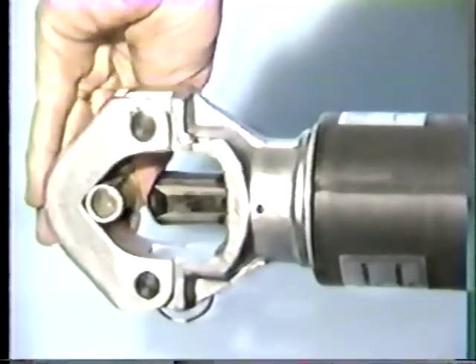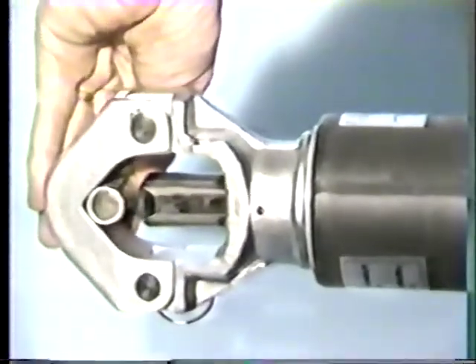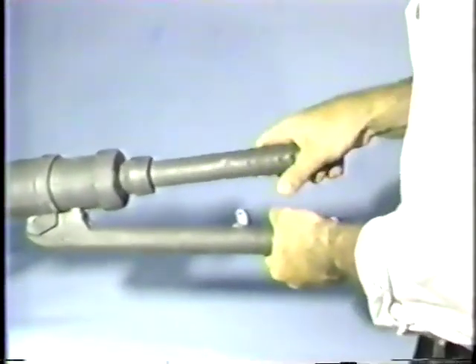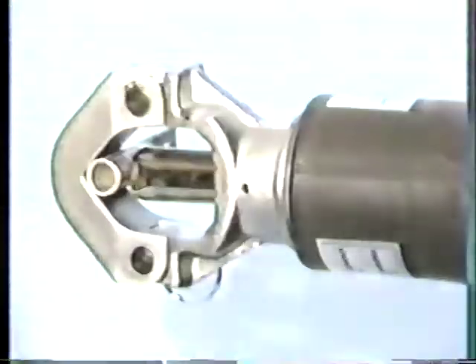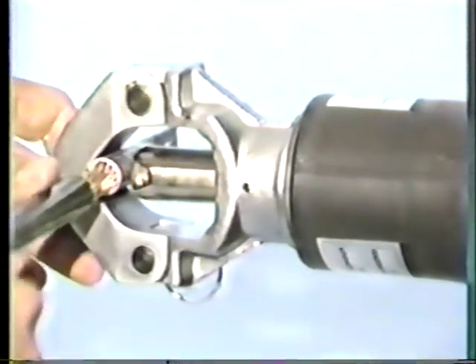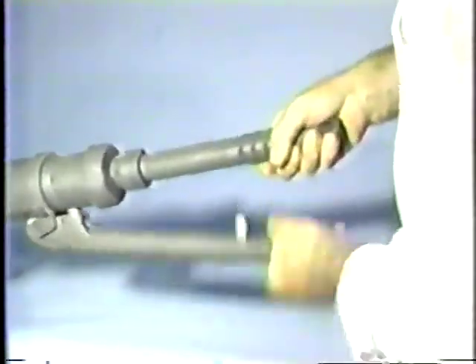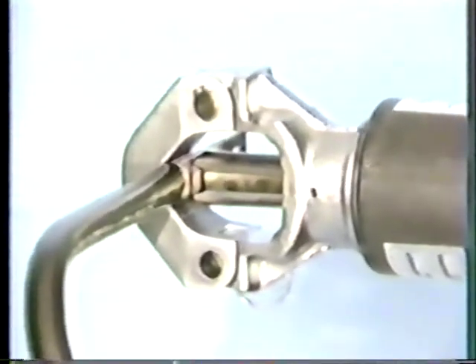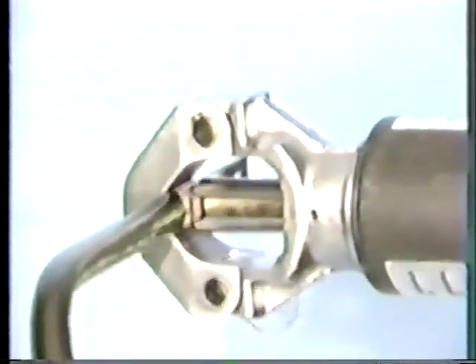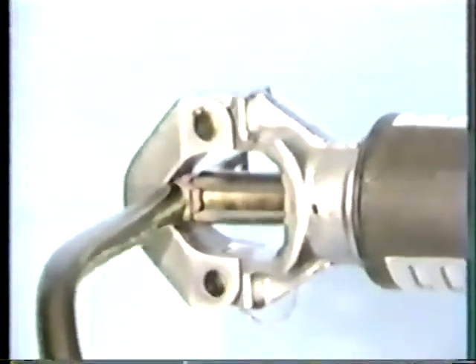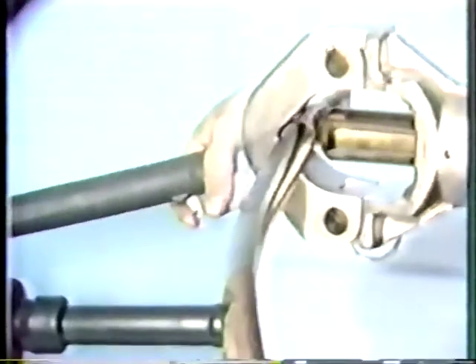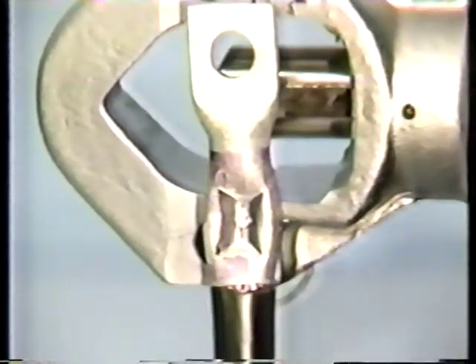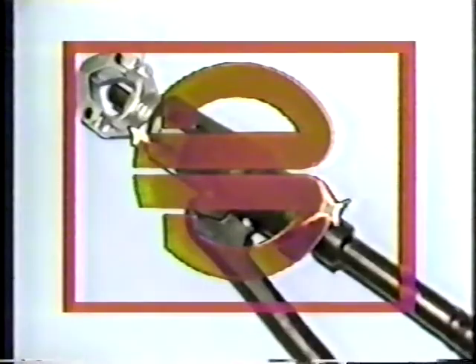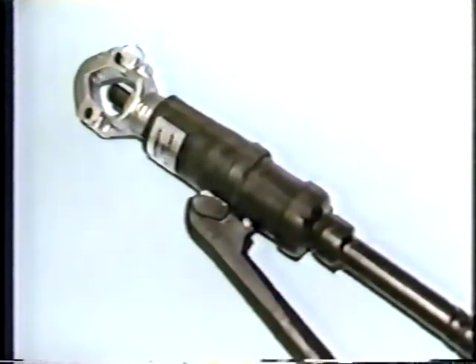Just insert the connector and rapid advance the ram by rotating the handle clockwise until an audible click is heard. Next, fully insert the conductor and pump the handle. When the crimp is complete, the tool's release valve will produce an audible blow-off with a sudden release of handle pressure. To remove the connector, simply squeeze the trigger while closing the handle. The Y644 dieless press provides a lower installed cost and eliminates costly production delays due to incorrect or lost dies at the job site.